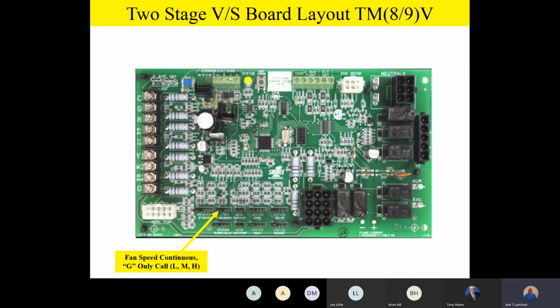So on this particular board, you're not actually selecting a speed tap like we did before on the TMY board. We're just giving it a selection of high, medium, low for continuous fan. If the homeowner just wants continuous fan, electrically, just a G call to the board, and that's the only call going to the board, how fast will that fan run? According to that jumper, high, medium, low. Again, about 35, 50, and 100% cooling airflow if you have a G only call. Any questions or comments so far on the jumpers?